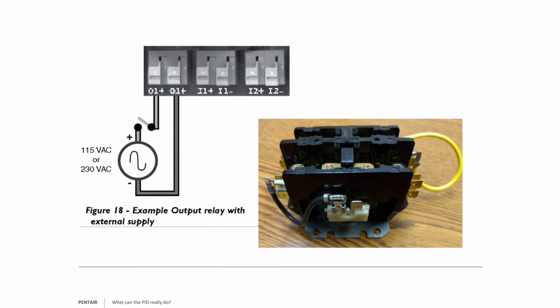Okay. Now another thing you can do is you can use a mag relay. Now granted, this is an older mag relay, but it works the same way. We have a line coming out going into our power supply, from our power supply going into the mag relay, from the mag relay going into our relay to complete the circuit. So when we want, say, a run condition, we set it to close under a run condition. The pump starts up because it sees a pressure demand, it closes the relay. We send 115 volts down to the mag relay, this magnetic relay, which energizes the coil and pulls the pump circuit closed, allowing the pump to start.